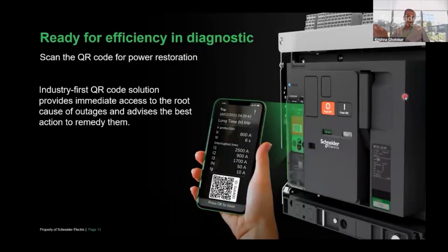Now the QR code on the breaker, even when the breaker has tripped, you can just scan the QR code and you get all the information of the fault. So all the troubleshooting information is available, and you can also proceed to the next step, like restoration of the power. So again, this is the first time you have a QR code displayed on the circuit breaker, which can give all the fault diagnostics or all the details.